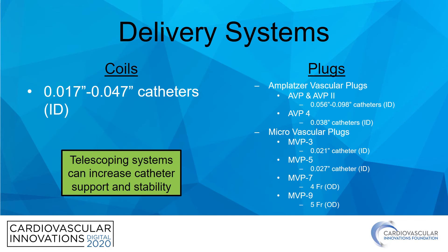The plugs each have their own specifications. The original AVP and AVP-2 can both be delivered through guide catheters ranging from 5 to 9 French. The AVP-4 requires catheters with an internal diameter of 0.038 inch. For MVPs, the 3 and 5 variety require catheters with internal diameters of 0.021 inch and 0.027 inch respectively, while MVPs 7 and 9 require 4 and 5 French outer diameter catheters respectively. Telescoping systems with catheters and sheaths can increase stability and support for device delivery.